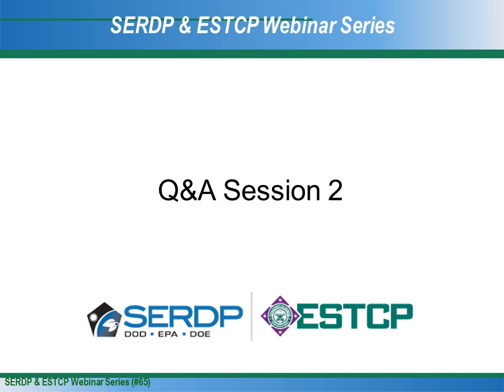So yeah, you just saw in Curtis's slides a really good set of slides showing the differences when he did this in Miami, or is it Texas? Yeah, Texas, Georgia, Atlanta, and North Dakota. When you have a heating climate where most of the energy in the building goes into heating, and you have low outside air temperatures, you're going to have a bigger benefit than in a temperate climate like San Francisco. As you saw from Curtis's slides, for cooling it depends a lot on whether you're in a dry climate or a humid climate, whether you're going to get an energy savings or not. So in general, using sealing for energy saving is going to be predominantly where you're heating dominated. The ASHRAE climate zones 4, 5, 6, 7, and up are the ones that really have the most benefit.